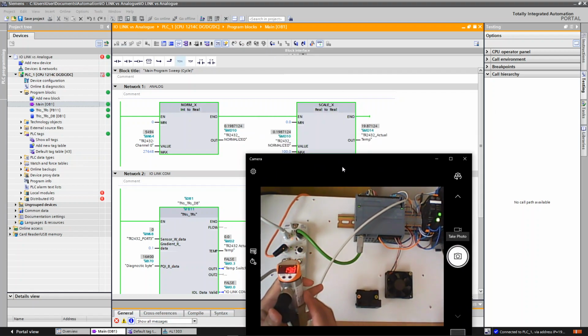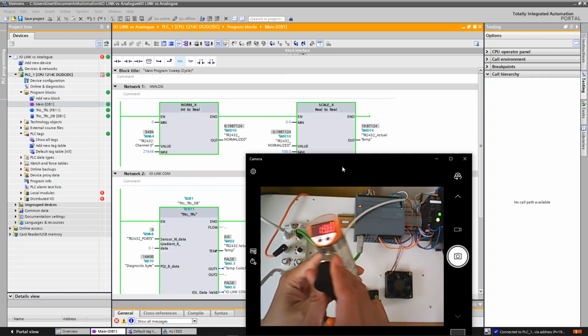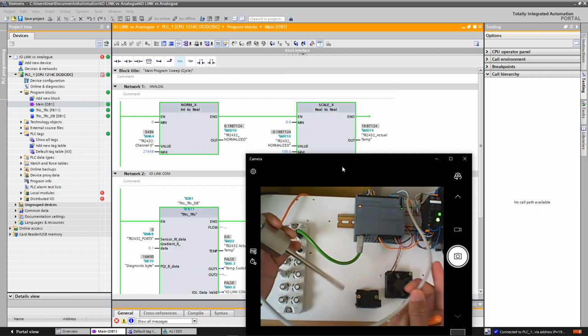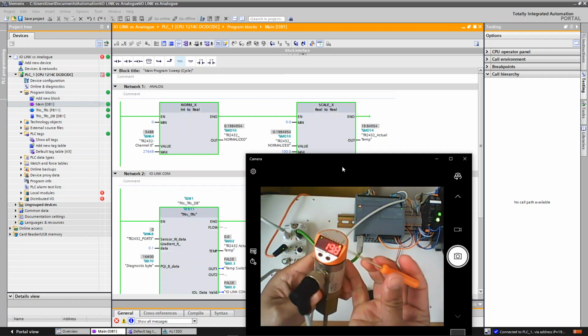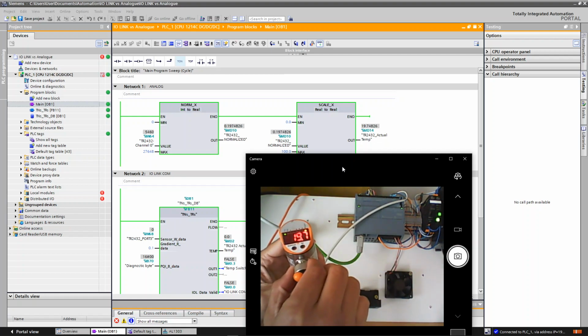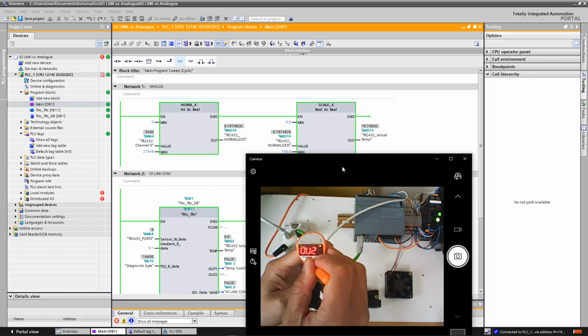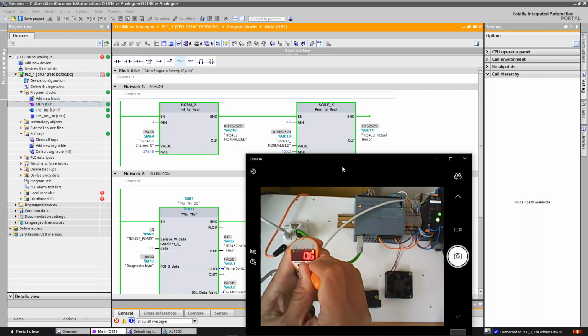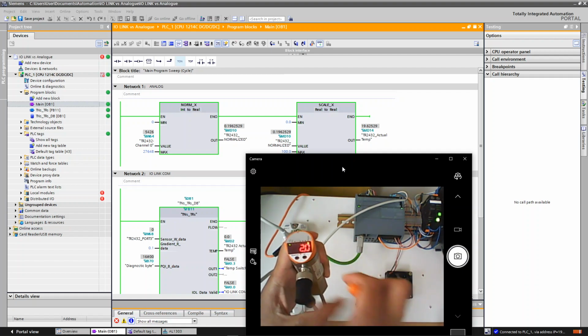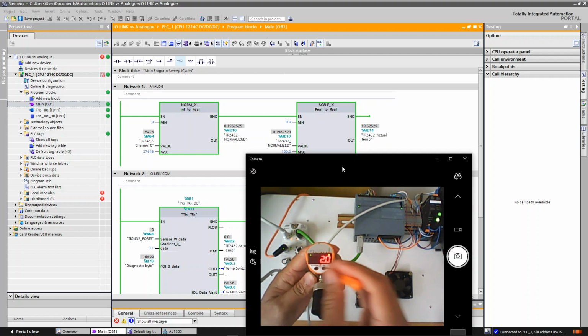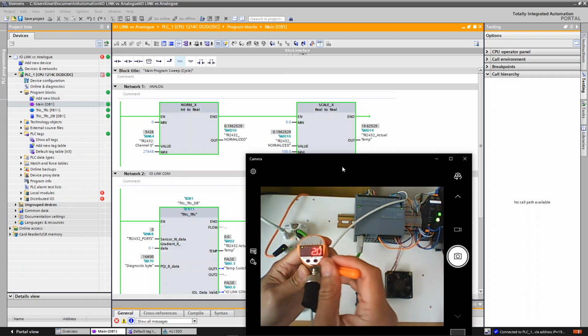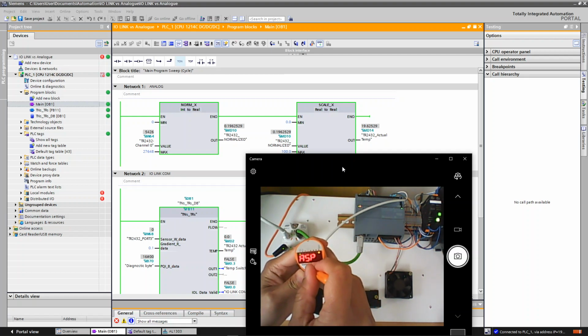So what are the common scenarios in the field? Let's say, for example, I connected this one directly to the analog input cards. Some operators like to play around, muck around with the sensor. So they have changed, for example, the analog start point, because the operators, or I'm an engineer that doesn't know what I'm doing. So sometimes it could happen in the field. If there is a button, they like to touch the button. So I changed the analog start point accidentally, for example, to 2.